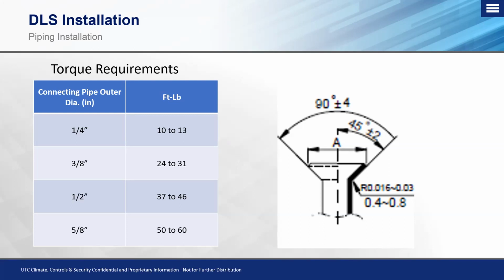And again, both of these processes are considered absolutely essential to any ductless installation. A dedicated 410A flaring tool, and dedicated torque wrenches to make sure that we're torquing down those fittings properly. Okay, good and tight will not cut it. If you overtighten them, you can crack the face of a flare and you'll start leaking refrigerant. Again, make sure you have the right tools to do the job right the first time.